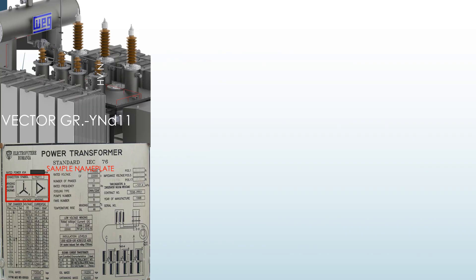Now we are going to test vector group of the transformer YND11. The YND11 transformer designates a specific winding configuration and phase relationship between primary and secondary winding. Specifically, it indicates a star connected primary with a neutral point to earth and a delta connected secondary winding.